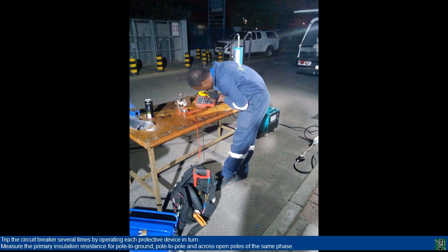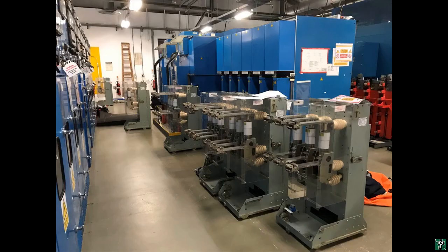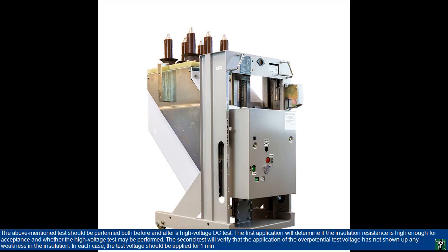Measure the primary insulation resistance for pole to ground, pole to pole and across open poles of the same phase. Perform insulation resistance tests at 500 VDC, using a megger or similar instrument, on all control wiring. Circuits containing semiconductor devices, such as solid-state protection relays, should not be tested. The above-mentioned test should be performed both before and after a high-voltage DC test.